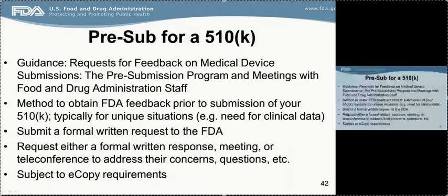So lastly, for the content of the 510(k), I want to provide you with some information regarding the pre-submission program. There is a guidance document titled Requests for Feedback on Medical Device Submissions: The Pre-Submission Program and Meetings with Food and Drug Administration Staff. This can be a valuable program. It is a way for you to obtain feedback from the FDA before the actual submission of your 510(k). But typically, a pre-sub for a 510(k) is only appropriate for unique situations, such as when you may need clinical data to support your demonstration of substantial equivalence.